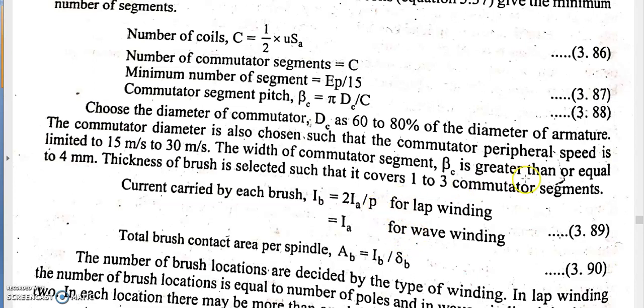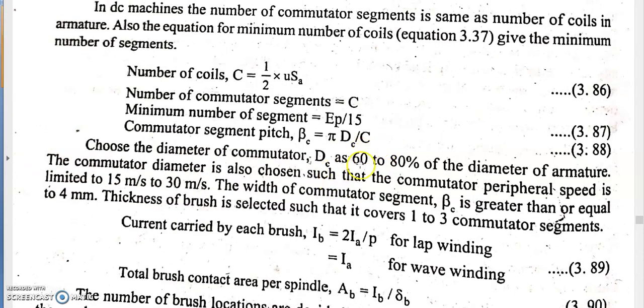The commutator segment pitch should be greater than or equal to 4 mm. That is the final objective in the design of the commutator. After calculating all parameters, the commutator segment pitch must satisfy this constraint. If it is not satisfied, the design procedure is revised and the segment pitch is recalculated.